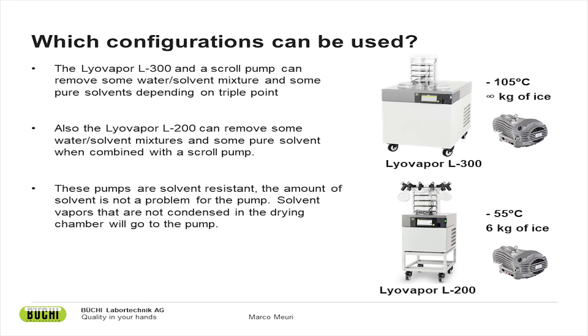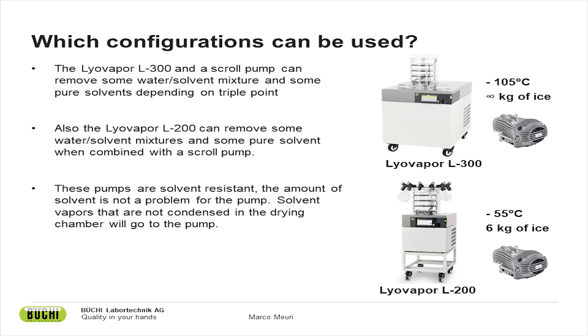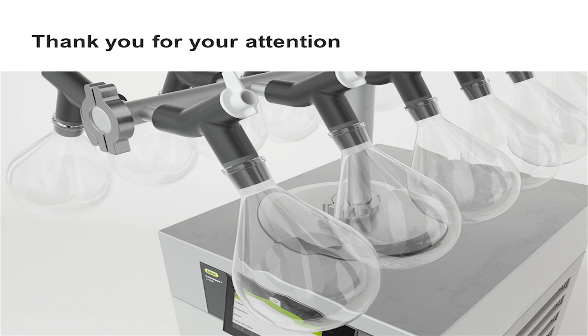The same approach applies to the L200, which is a -55°C, 6 kg system. If equipped with a scroll pump, it can handle many organic solvents — acetonitrile up to 50%, and certain concentrations of ethanol, methanol, and IPA — under the condition that the solvent portion will not melt, which is the case with any freeze-dryer used for those solvents. If freeze-drying of organic solvents is a relevant topic for you, I hope this webinar has been useful. Please don't hesitate to contact us — we are very happy to help you find the right machine and the right conditions for your organic solvent freeze-drying needs.